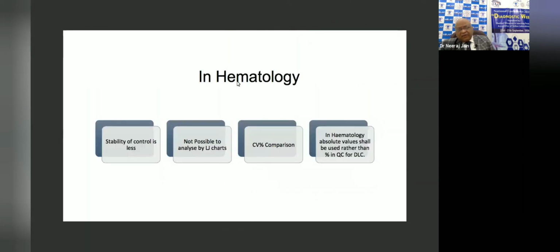But in hematology, the situation is a little different because stability of controls is less. It is not possible to analyze by LJ chart because you will calculate your monthly mean, and next month you will get a new lot. You cannot use the previous month's mean and standard deviation for that lot. Then what can we do? We can compare CV percent. For every lot, you calculate CV percent and you compare this CV percent.